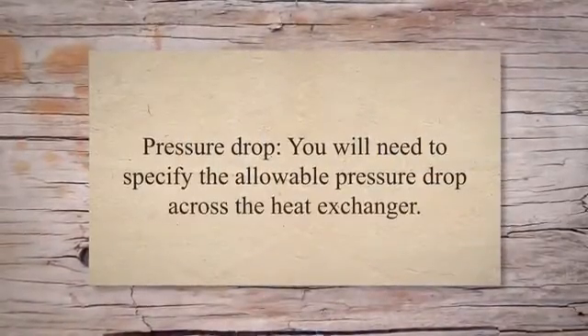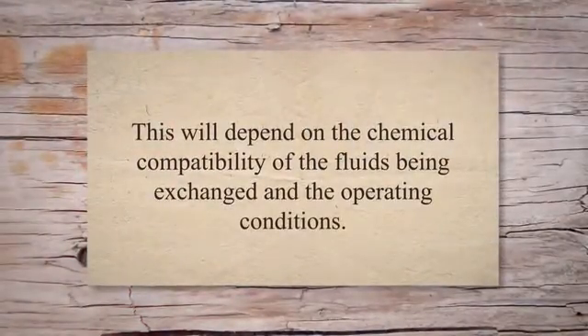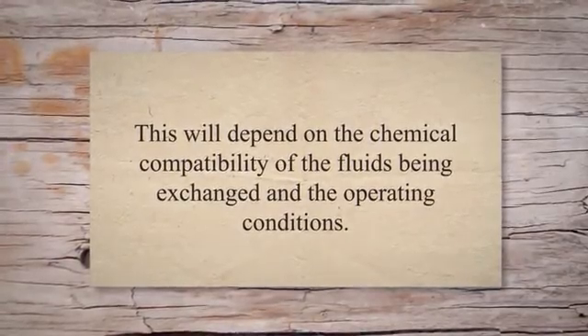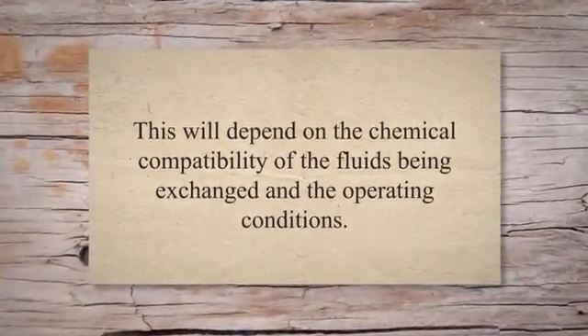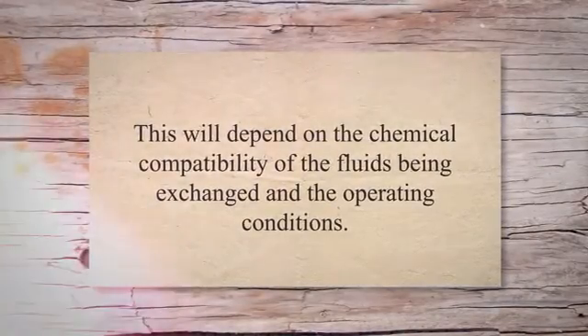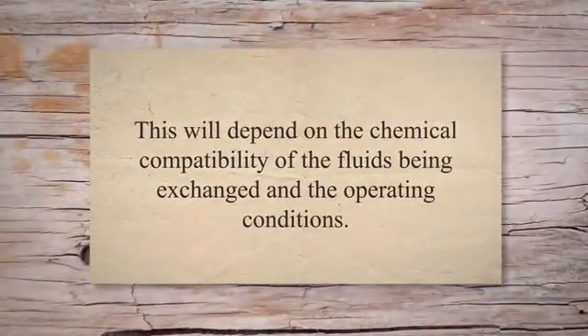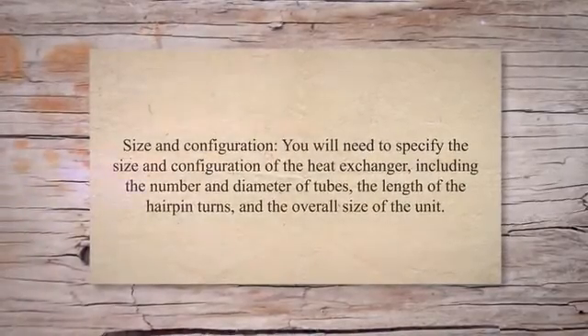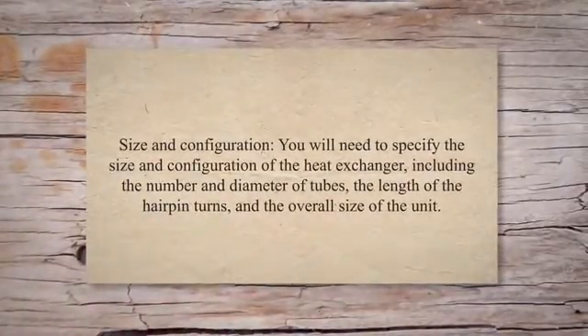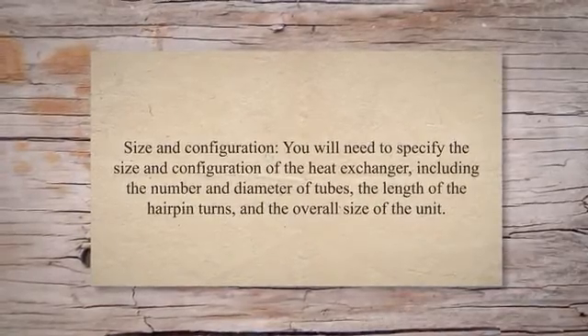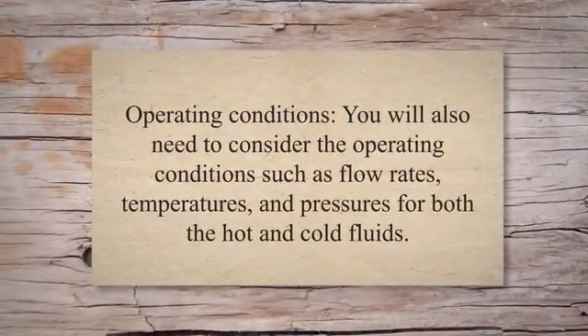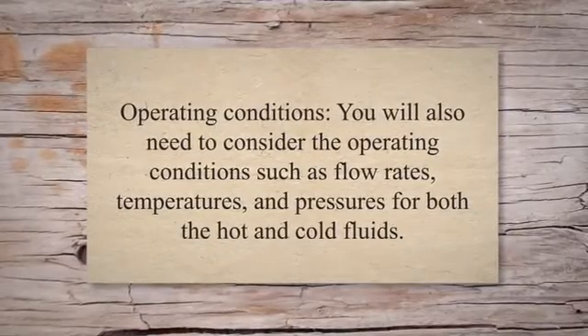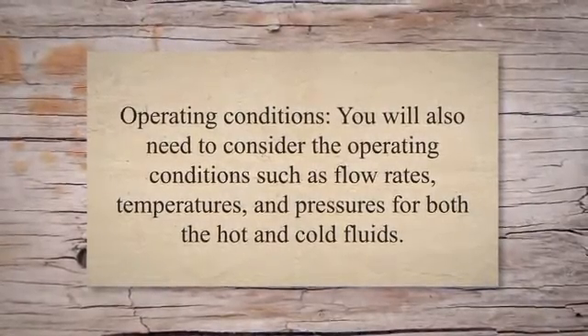Additional specification factors include the allowable pressure drop across the heat exchanger, the materials of construction for tubes, shell, and baffles (based on chemical compatibility and operating conditions), and the size and configuration including the number and diameter of tubes, length of the hairpin turns, and overall unit size. Operating conditions such as flow rates, temperatures, and pressures for both the hot and cold fluids must also be specified.